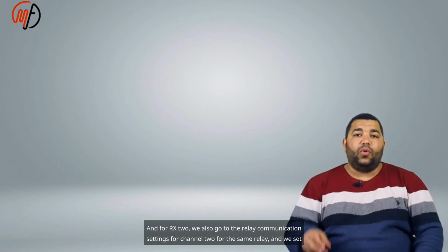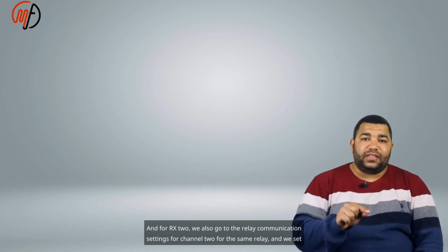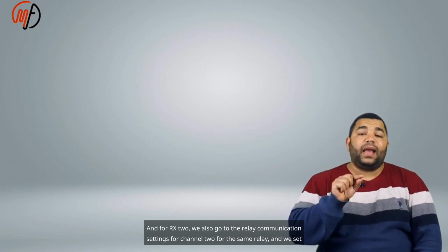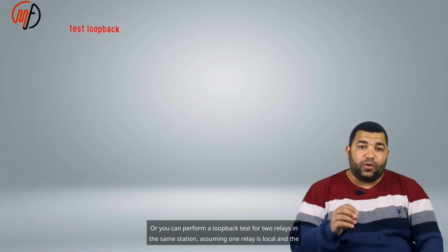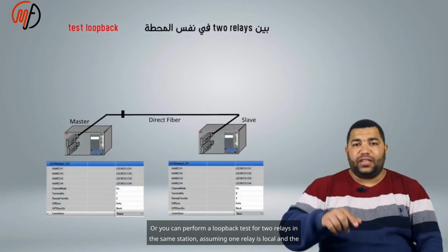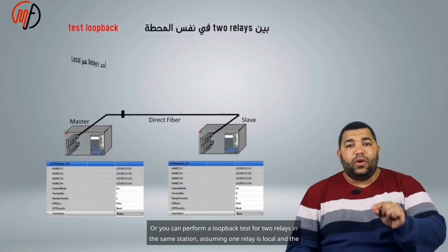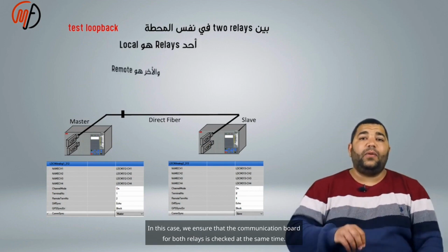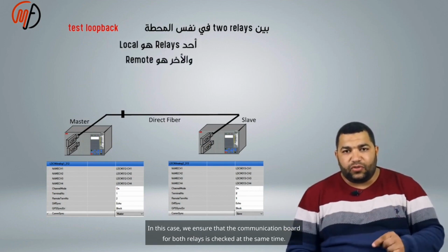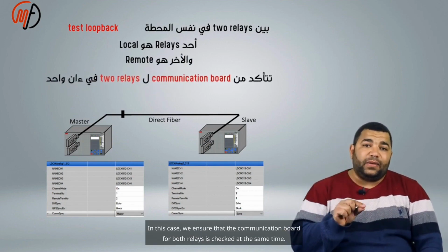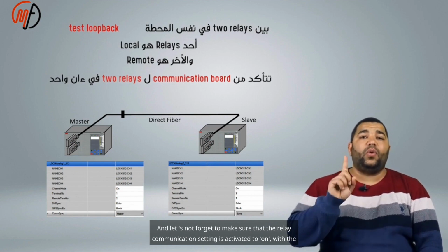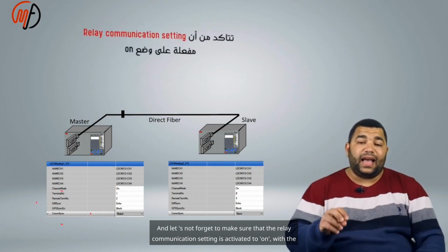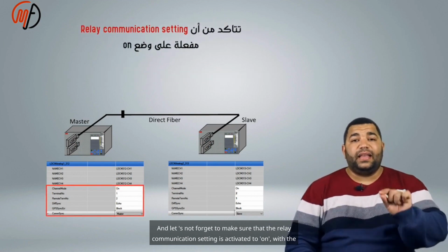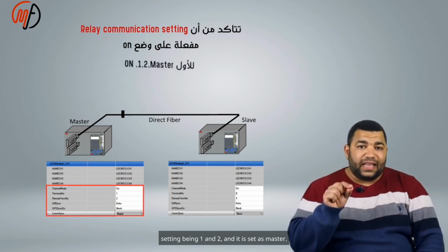And for RX2, we also go to the relay communication settings for channel 2 for the same relay, and we set TX2 and RX1. Or you can perform a loopback test for 2 relays in the same station, assuming one relay is local and the other is remote. In this case, we ensure that the communication board for both relays is checked at the same time. And let's not forget to make sure that the relay communication setting is activated to on, with the setting being 1 and 2, and it is set as master.